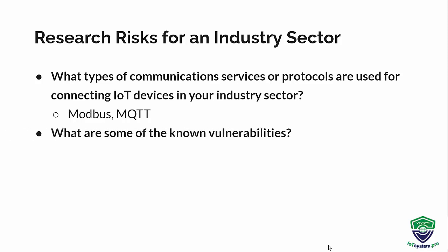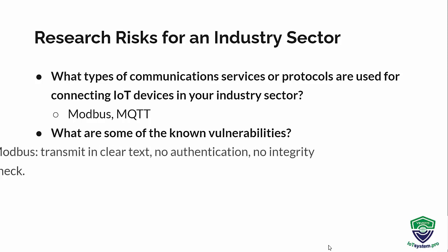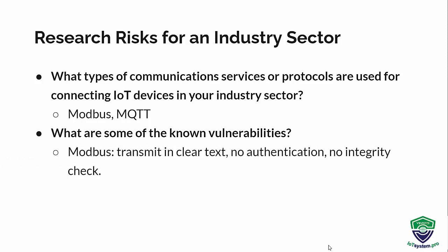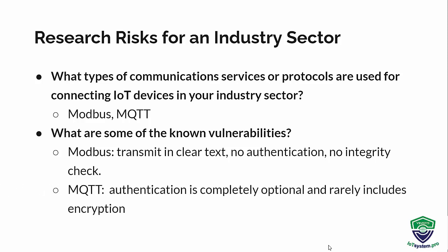The next question is, what are some of the known vulnerabilities? Modbus transmits in clear text, with no authentication and no integrity check. For the MQTT protocol, authentication is completely optional and rarely includes encryption.